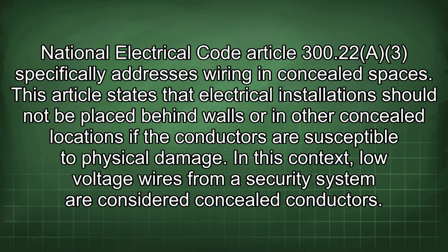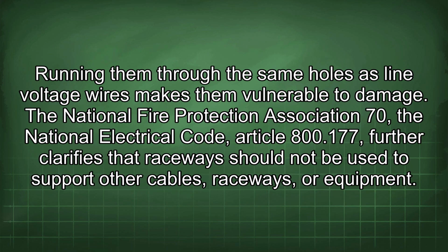National Electrical Code Article 300.22 specifically addresses wiring in concealed spaces. This article states that electrical installations should not be placed behind walls or in other concealed locations if the conductors are susceptible to physical damage. In this context, low voltage wires from a security system are considered concealed conductors. Running them through the same holes as line voltage wires makes them vulnerable to damage.